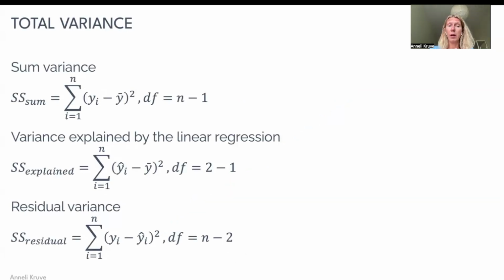We have the total or sum variance, which means the variance across all points relative to the mean signal of the whole calibration graph. So not on a specific concentration level, but across all of the calibration graph levels, all measurements that have been done. This is basically like a horizontal line in our calibration graph, and the points at low concentration are lower and at high concentrations are higher. Therefore, this indicates how much in total the signal of these calibration graph measurements is varying.